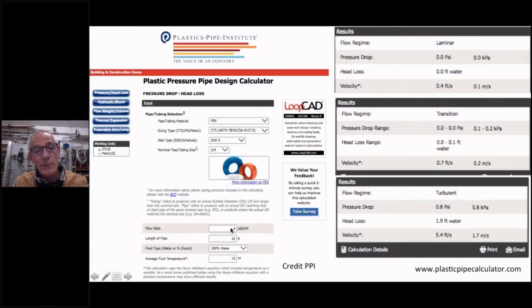So then I just kept playing with this formula and putting different GPM numbers to see where it went into transitional flow. So there you can see a point where I went into transitional flow, and then I wanted to see where I got up into turbulent conditions. So somewhere about 0.5, just over half a gallon per minute, I got up into this condition here, which would be good for transferring heat, out of that pipe into whatever it might be, a slab, or into a heat emitter of some sort.